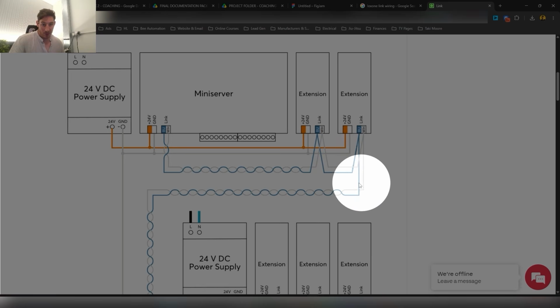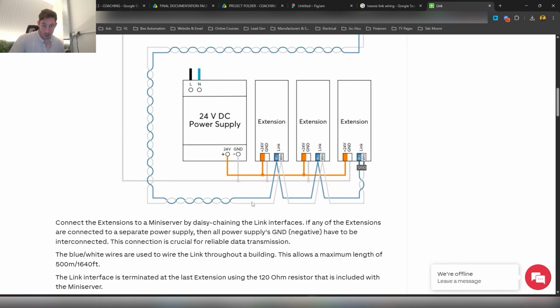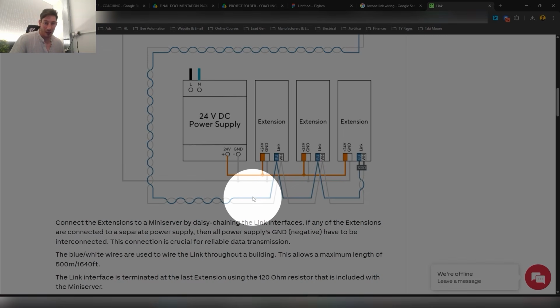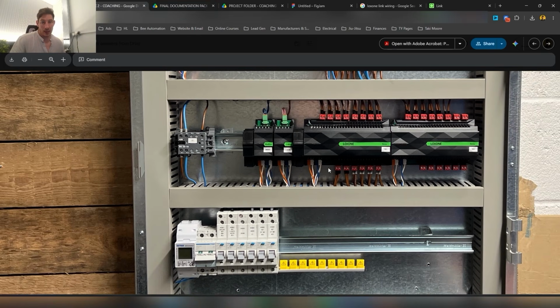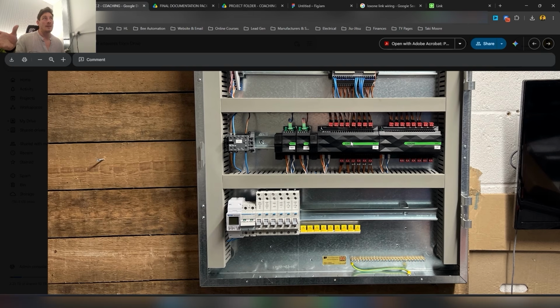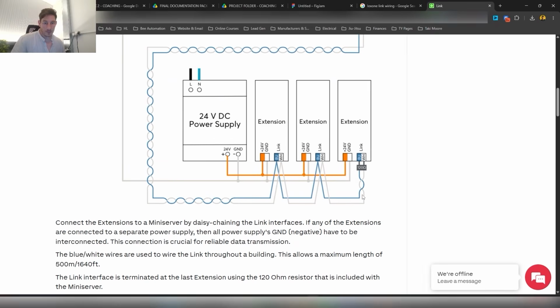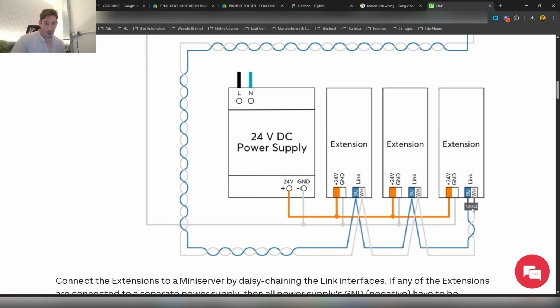Then let's just say we've got some terminal blocks here at the bottom of Lox 1, and this is a cat cable out in the field, and then we've got some terminal blocks here in the second panel in the garage. We're continuing that Loxone link to the various extensions because we haven't got a mini server in this panel. If we were using a two mini server setup, we wouldn't have to do this. But because we've got one mini server, one link output and communications, this is why we're doing that. And then at the final extension, we're putting that 120 ohm resistor.